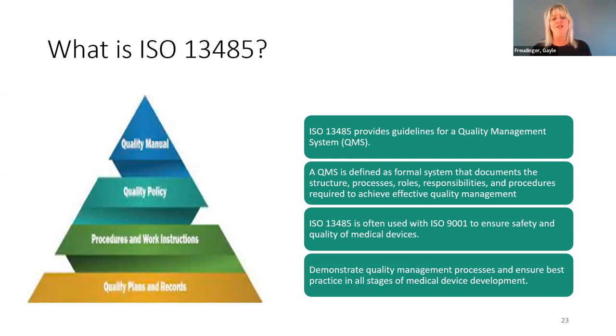But the FDA doesn't follow the ISO 13485. It has different requirements for quality management that we just mentioned in the design piece in the slide before. So the design controls by the FDA are defined under FDA 21 CFR 820.30. But ISO is known internationally, and a lot of people tend to possibly work with a manufacturer who could be located in Europe or Korea or somewhere else. And so they're following the ISO 13485. So how does that compare to what the FDA is requiring?